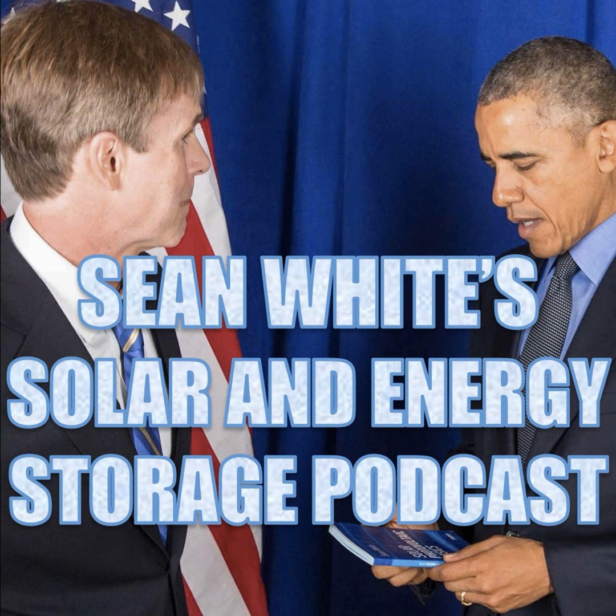Direct PV system. What a direct PV system is, is when you don't have any energy storage, you just have PV connected to a load, and cows like direct PV. So that's probably the most common type of direct PV: pumping water. Sometimes it's a fan, just blowing in your roof. It's good to have a direct load. You need more when it's sunny. Your tank is your battery. In this particular case, the cow's drinking out of the watering hole. That's your tank. That's your battery. So during the day or sunny days, you fill up the tank. And then if you had really rainy, cloudy weather, well, you're probably not going to need a whole lot of water. And at night, you've got the water there in case they get thirsty at night.